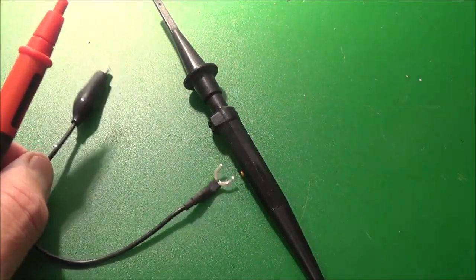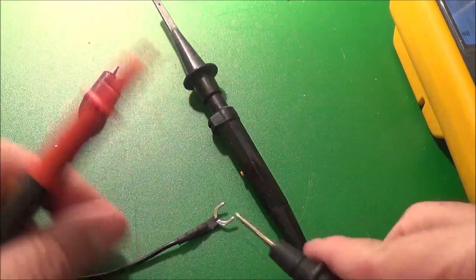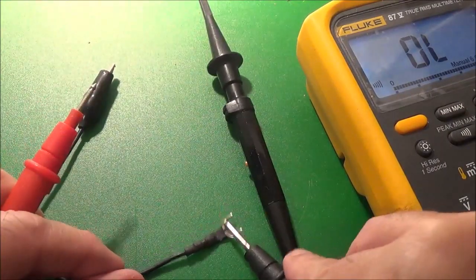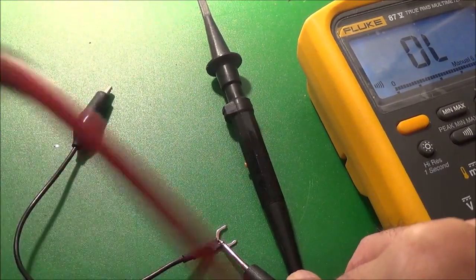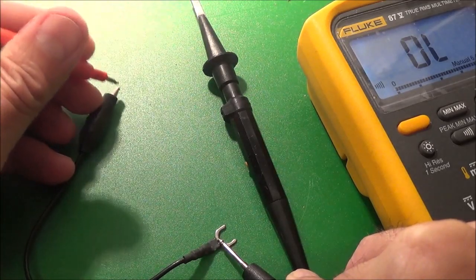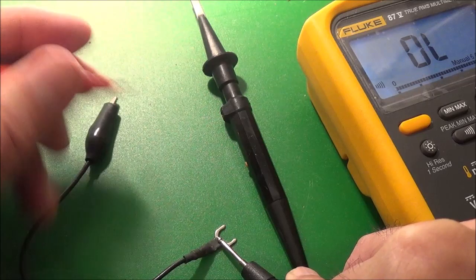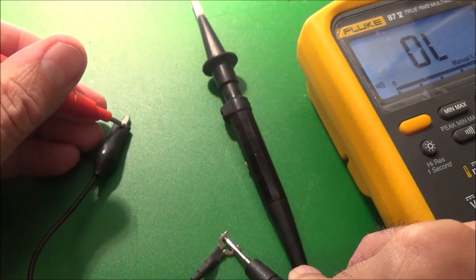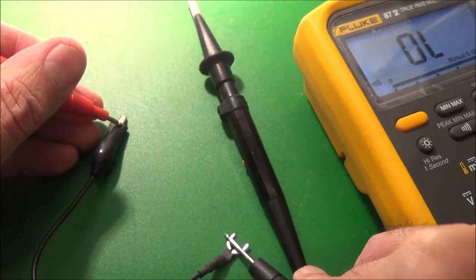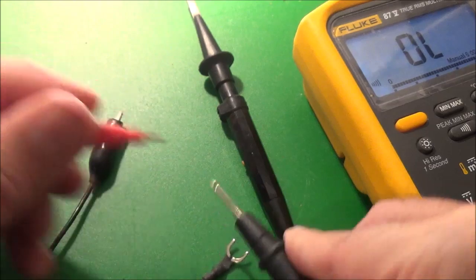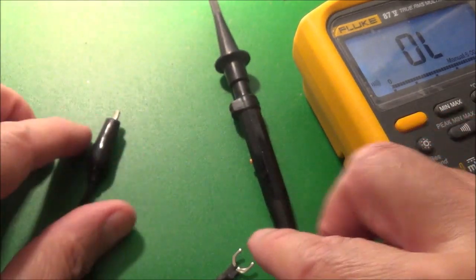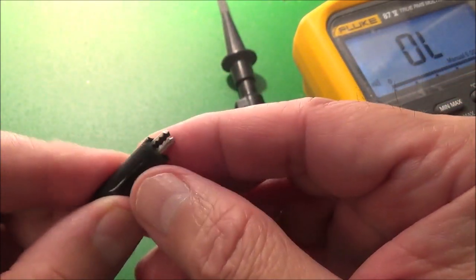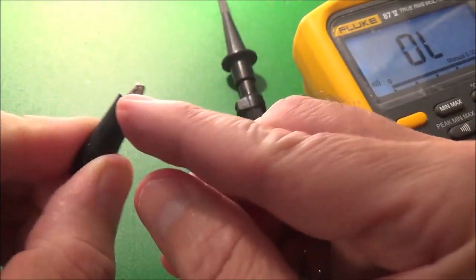So next I'm going to check the little ground wire here, or ground cable, because that is actually easily accessible. That's odd. I should get something here but I'm not getting anything at all. So I'm going to take a closer look here. Most likely the problem is going to be at the ends.